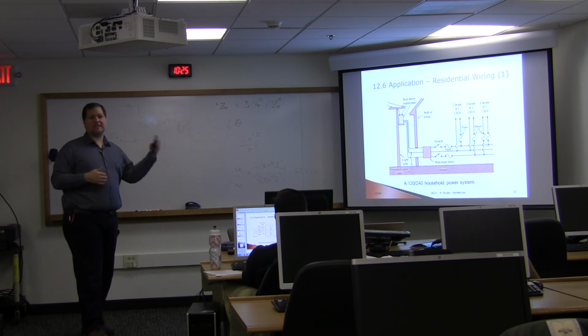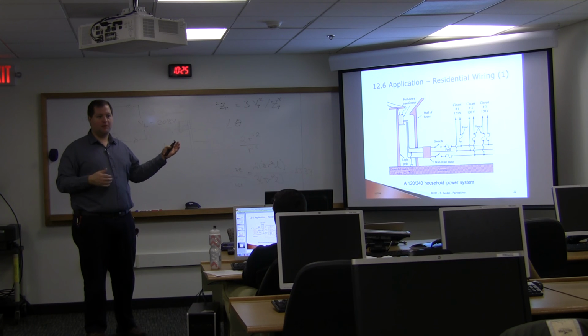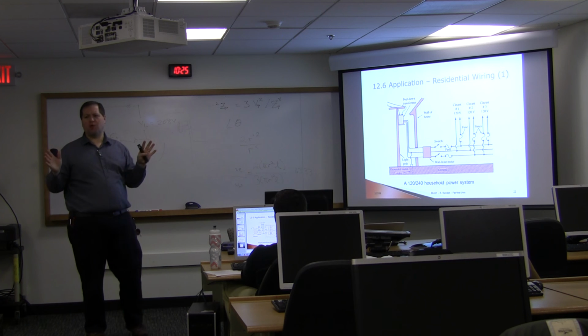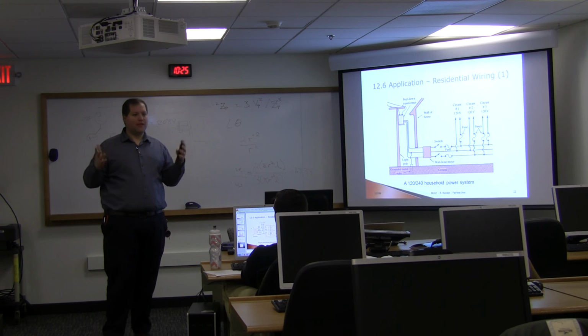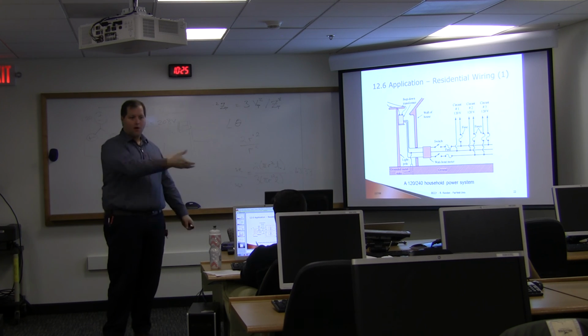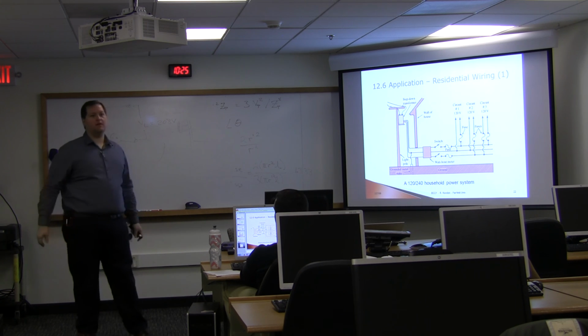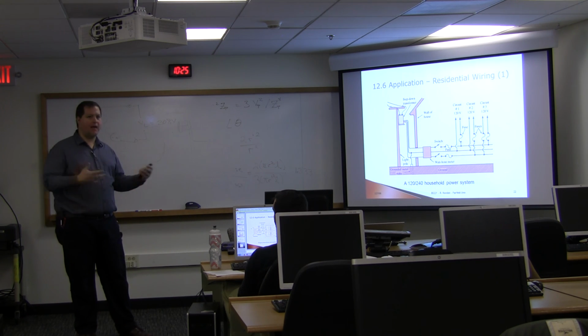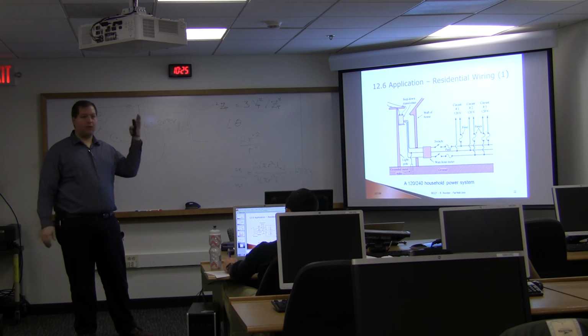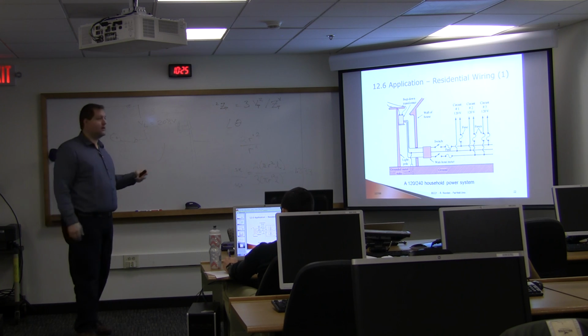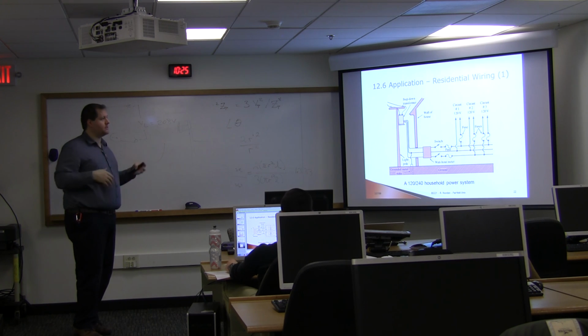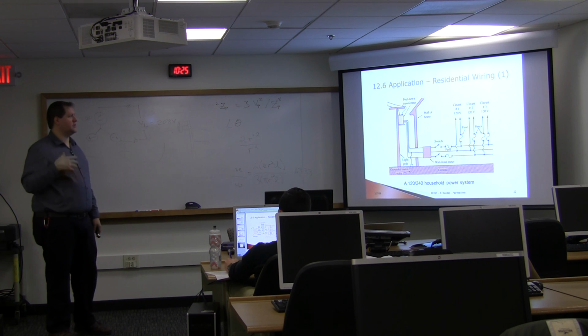It wouldn't be safe to put a 60 amp breaker in the distribution panel with wire that can only carry 40 amps, and say you'll just never plug in anything that takes more than 40 amps. That's really dangerous, because the next person who comes into that building may say, hey, look at that plug, I can plug this giant thing into it—I'm going to plug my stove in, my stove takes 60 amps—and whoops, they cause a fire because they pull too much power and the breaker won't cut off and protect it. So a lot of what you hear about in terms of regulations is really oriented around safety.